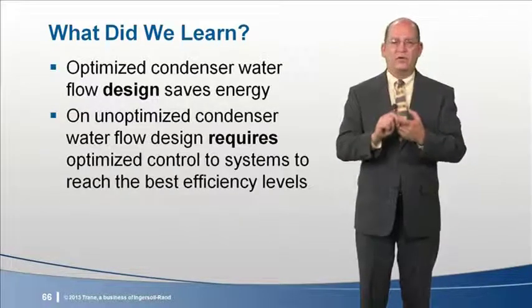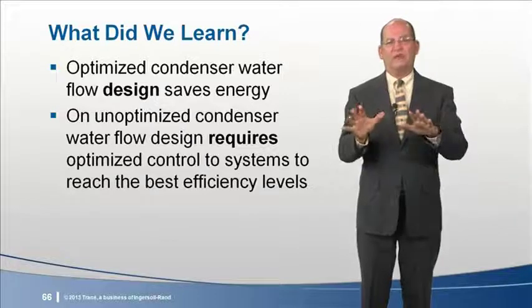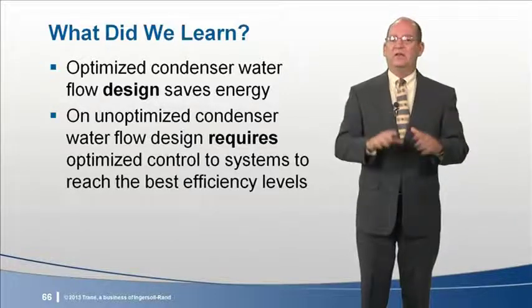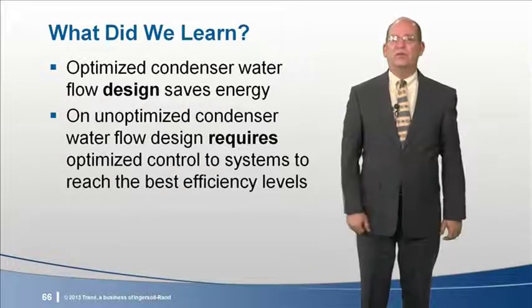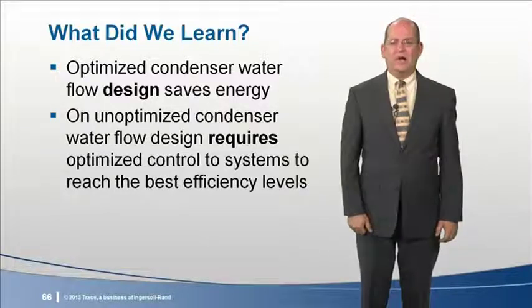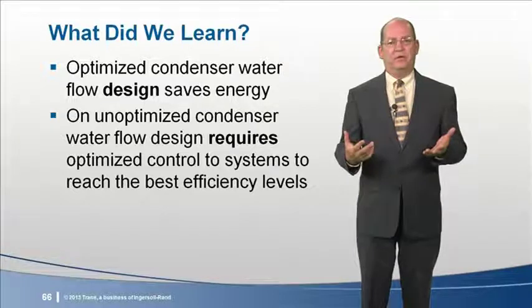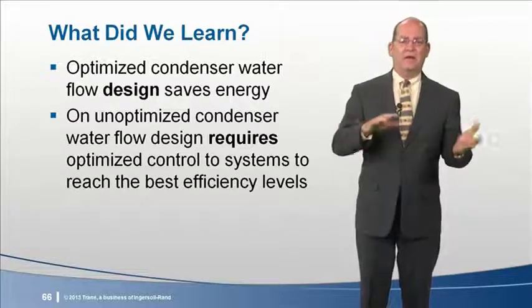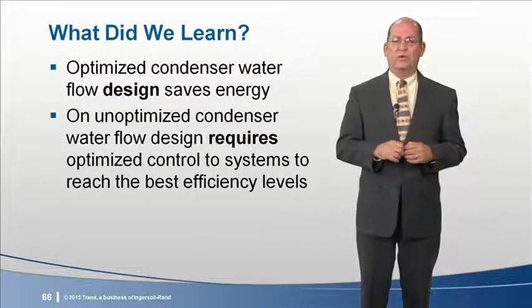Designing for a lower flow rate, for example, 1.5 or 2 GPM per ton, gives very similar performance to a system using an unoptimized condenser water design flow rate of 3 GPM per ton and dynamically optimizing the condenser water flow rate.